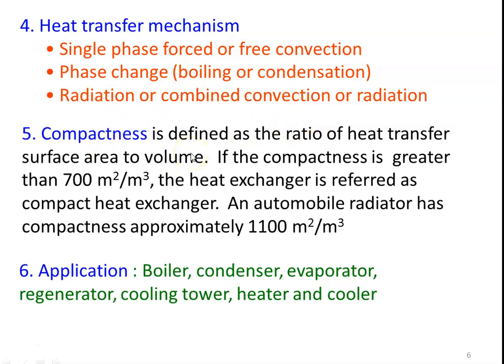Another method of classifying heat exchangers is compactness, defined as the ratio of heat transfer surface area to volume. When this ratio is greater than 700 m² per m³, the heat exchanger is referred to as a compact heat exchanger. The automobile radiator is an example of a compact heat exchanger, with a compactness of approximately 1100 m² per m³, meaning the total heat transfer area is very high compared to the overall volume of the radiator.